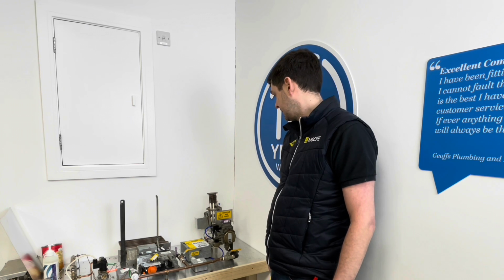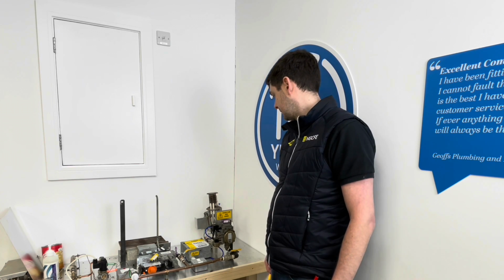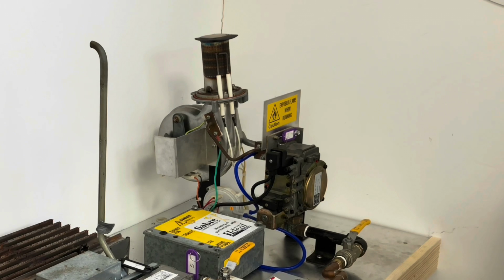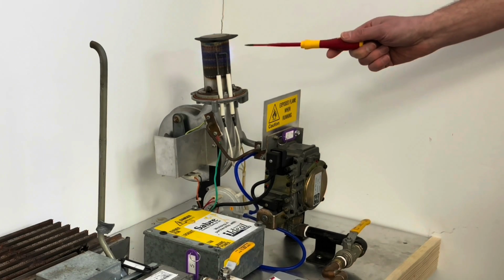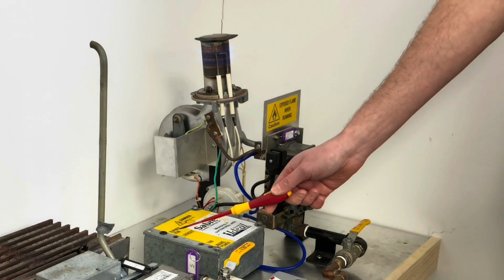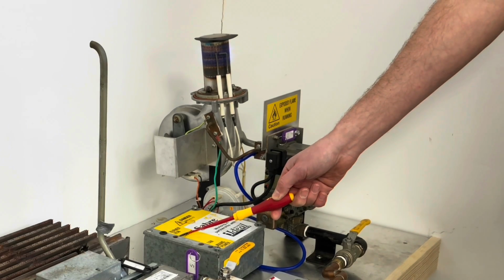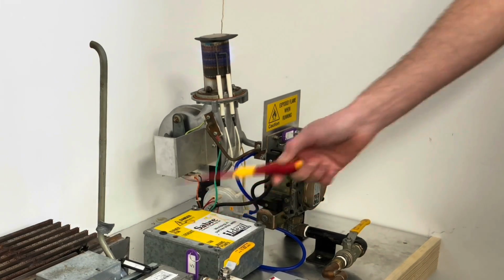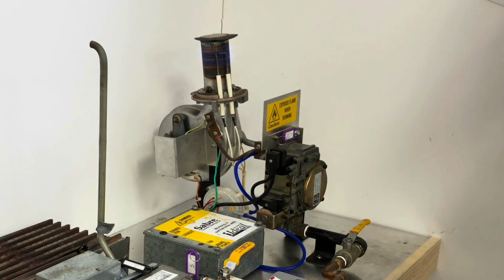Fan's purging, trying to ignite. It lights and instantly stops trying to ignite, and now we've got a burner-up light on the board, identifying that there's a flame sensed, there's a flame established because there's DC current back at the board.